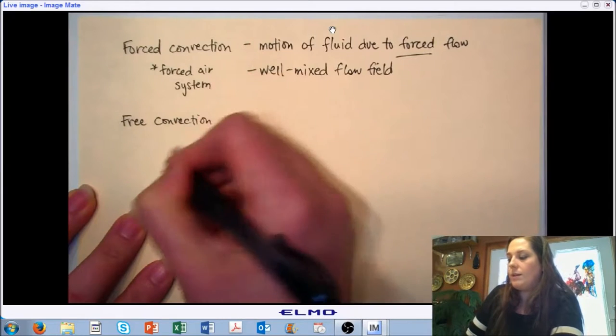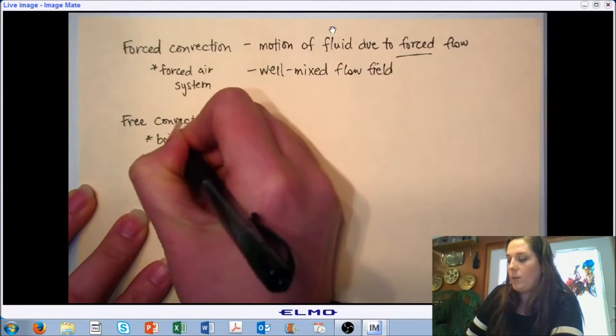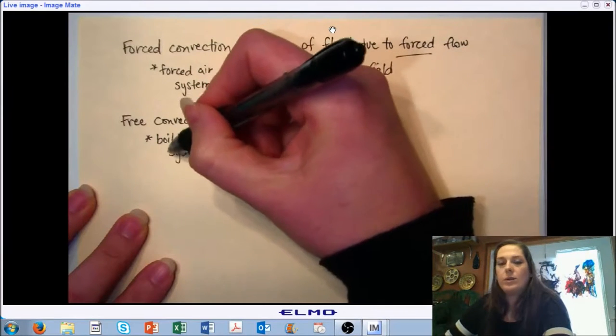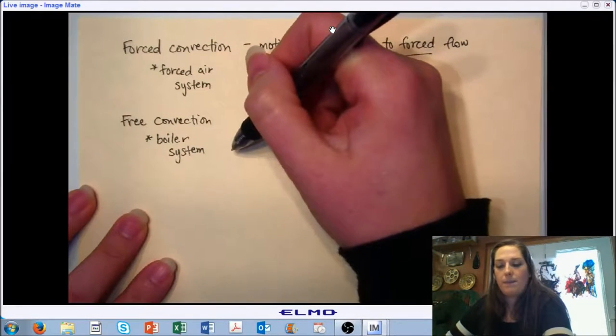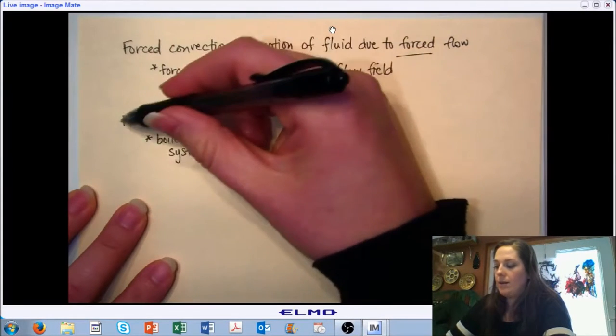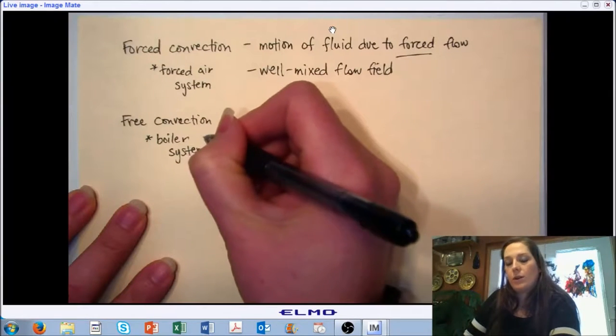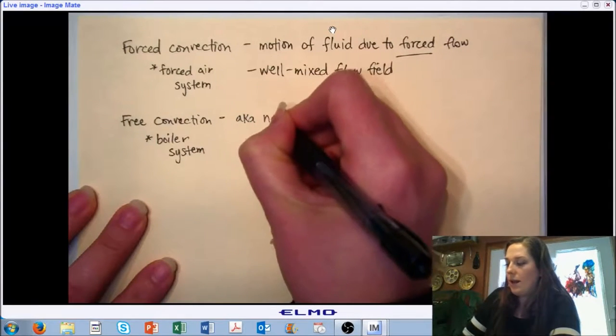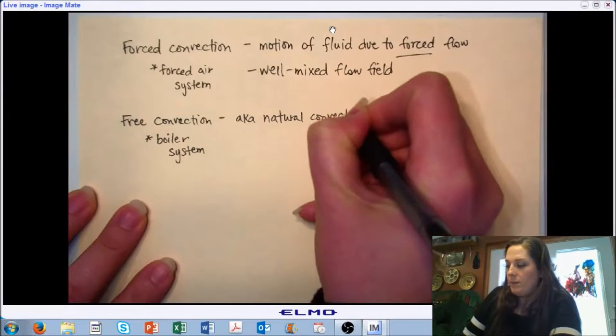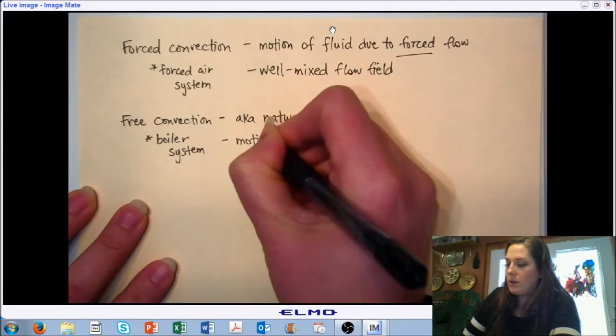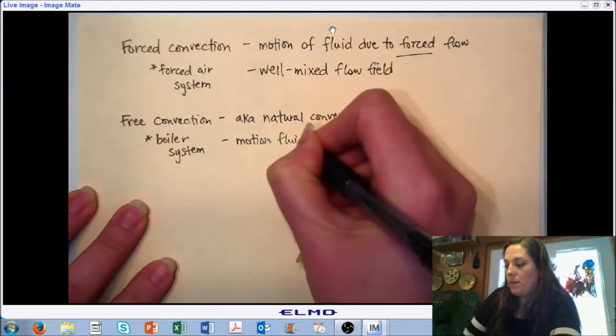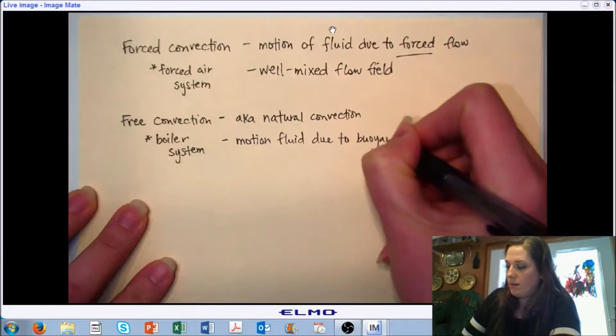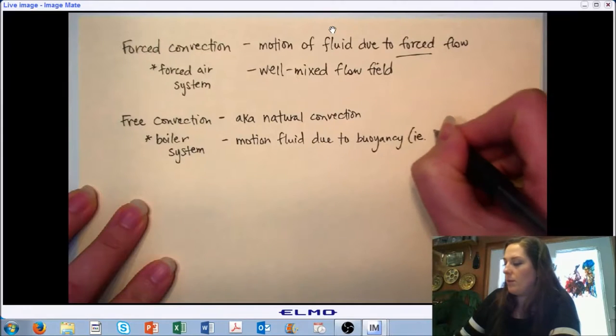For free convection — also called natural convection — when we are analyzing it inside a building, we're looking at things like a boiler system where we may be delivering hot water into a set of pipes acting as a heat exchanger into a room, with no air being forced over them to transfer heat. The motion of the fluid and the mixing is due primarily to buoyancy effects resulting from fluid density differences.